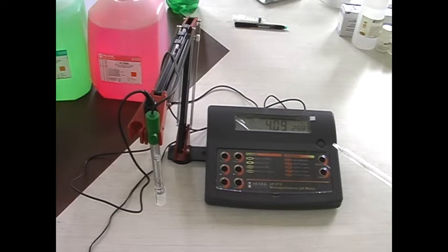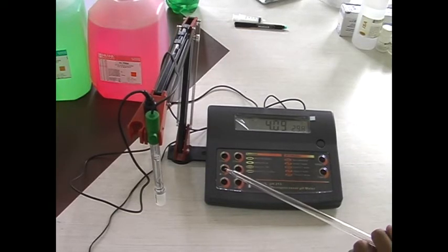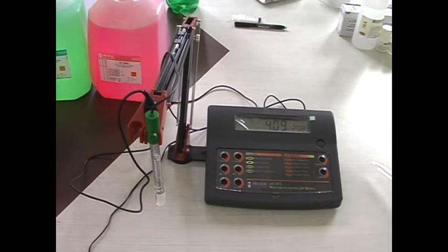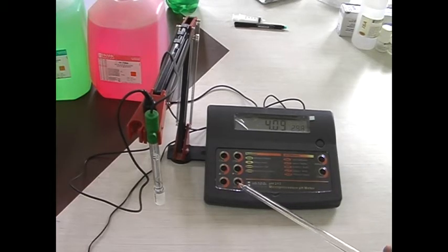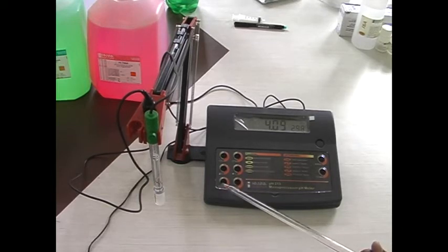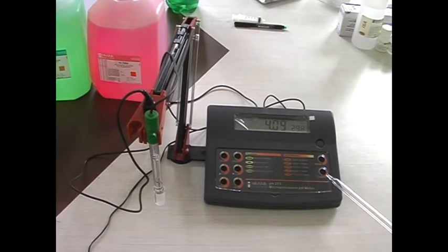This is the up arrow key to manually increase the temperature or to select the pH value. This MR key is to recall the stored value. Then this is a MEM key, memory key, to store a value in the memory. Then on this side, this is a COMM communication key. This is to set the baud rate. Now this is a range key. The range key is used to select the measurement range. You can select the pH range or you can select the millivolt range. This is the on-off key. It is used to switch on or switch off the instrument.